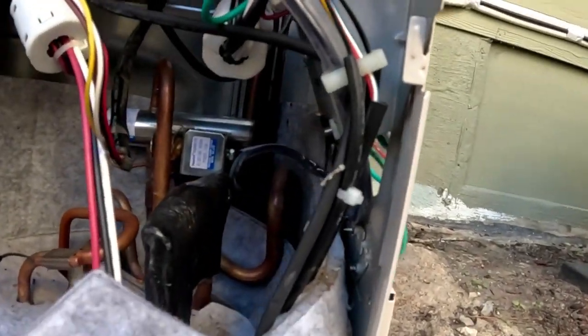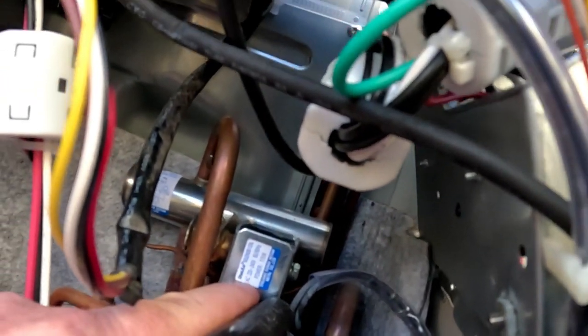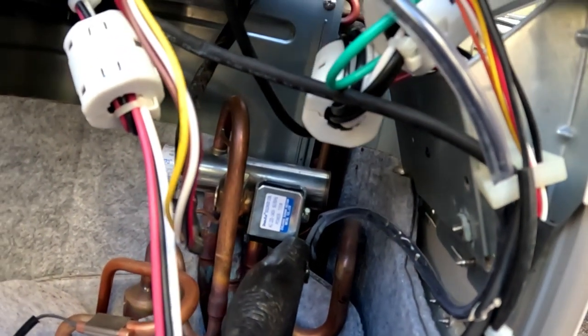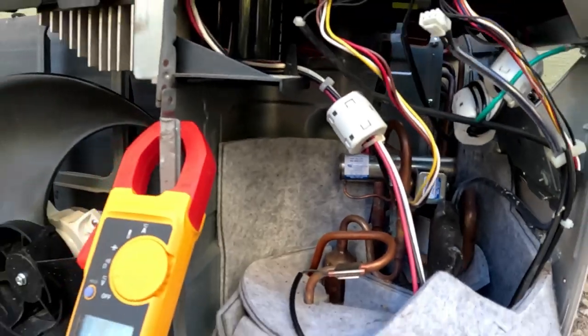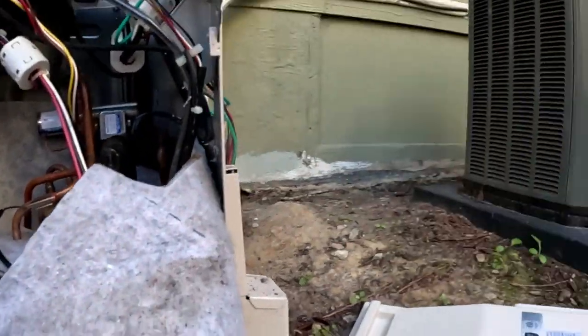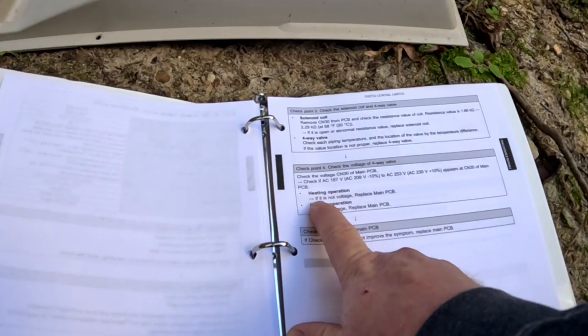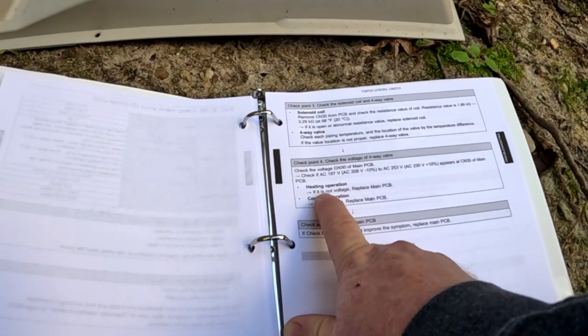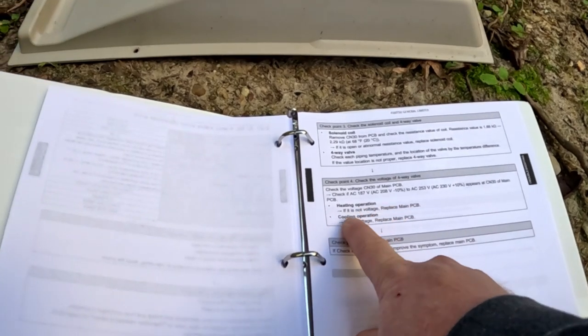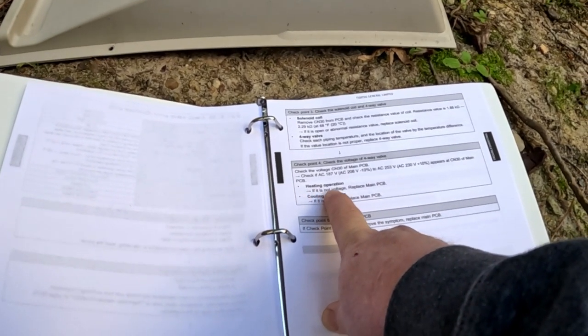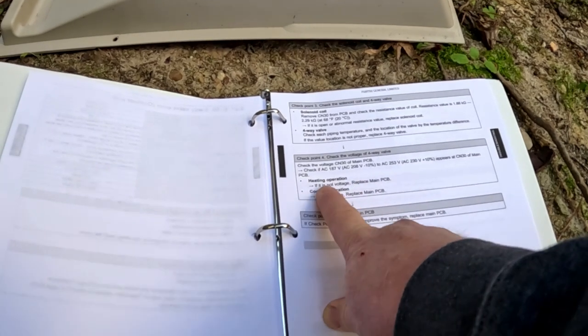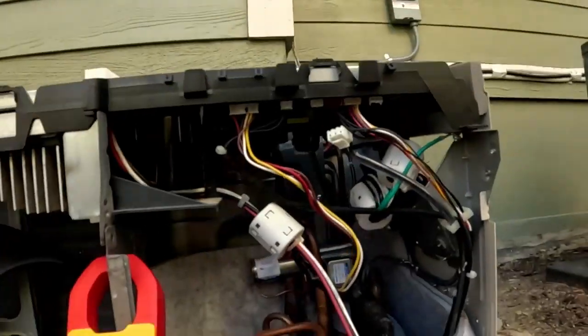So it's odd that that would be, yeah, the voltage on that solenoid right there, 220 to 240. 220 to 240. So yeah, there's a high voltage solenoid in a Mitsubishi Mini-Split. It's telling me right there, if it is not voltage, replace the main board. I guess that's Asian English. If there is not voltage, I would think it would say that, replace the board. We don't have voltage.